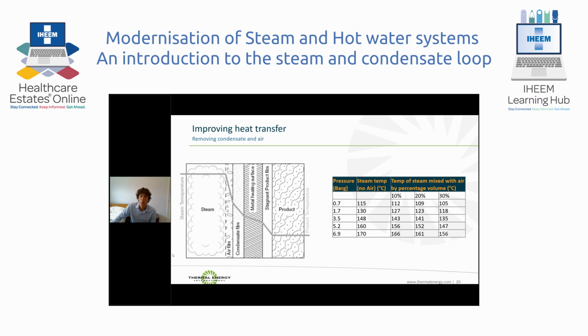Water entrained in the steam also reduces the heat content proportional to its mass fraction. So if we only have 90% dry steam, it means we're only getting 90% of the energy out of that steam at the point of use in the heat exchanger.